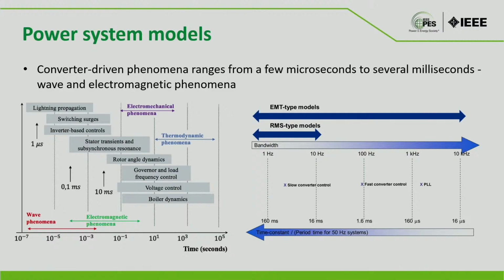Try and link this right hand side of the figure to the left hand side. There are horses for courses. What do you really want to study? What's your objective? If it's lightning phenomena or switching surges, no RMS model can give you insight, you need to go to EMT model. Do you want to look at the impact of PLL dynamics? If you've got a corrupted voltage waveform, the PLL would struggle to latch on to the system, and it would compromise the performance of the inverter based control. Then again you need EMT model. But if you're just interested in line loading, okay if I trip one line, what's the load on the second line, you're probably okay to use RMS model, because that's perfectly fine if you're looking at transient stability. In a high synchronous machine dominated area, probably it's okay to use RMS model.